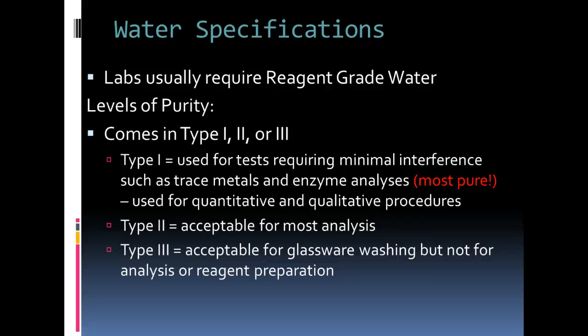Type 2 is acceptable for most analysis, although type 1 is the choice. And type 3 is acceptable for glassware washing, but we wouldn't use it to make our reagents or anything.